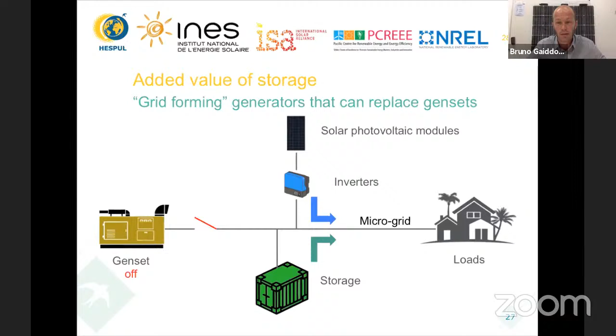With storage, you can oversize the PV system. If there's excess production, it's used to store energy, and this stored energy is injected into the microgrid at the end of the day. Once the battery is empty, the genset switches on again to supply electricity during the night. If the storage is large enough, it can deliver electricity through the night for a fully PV-supplied microgrid.